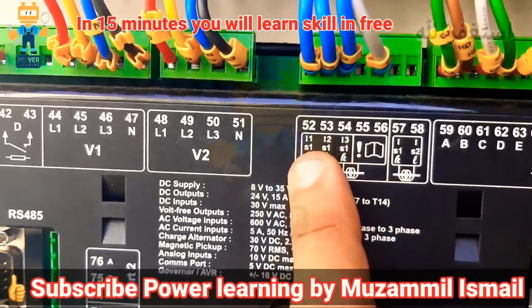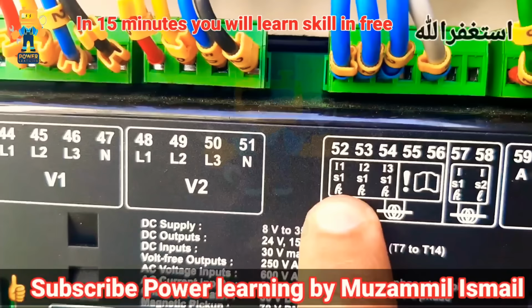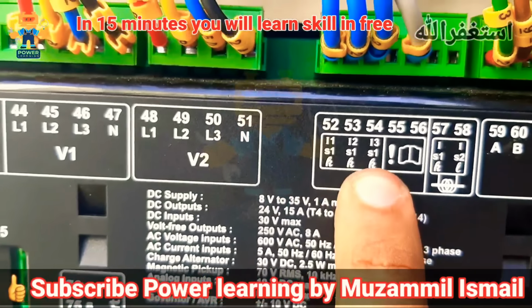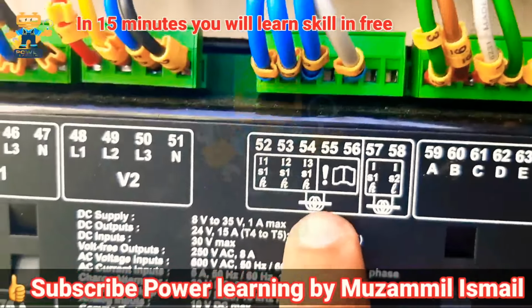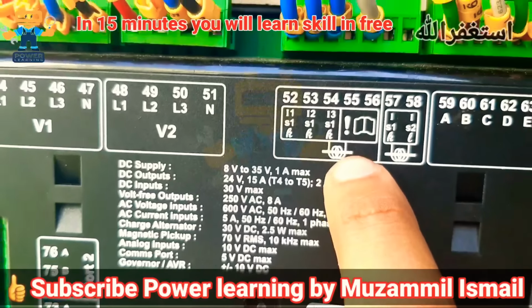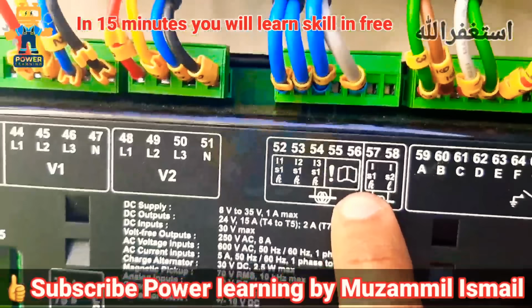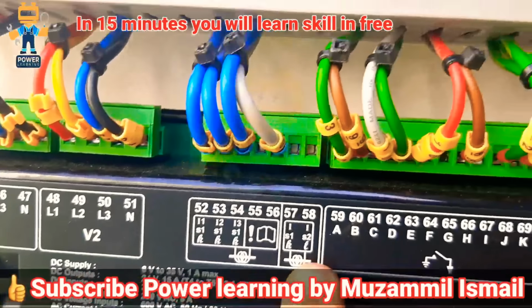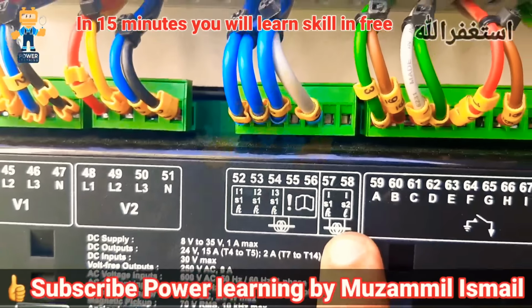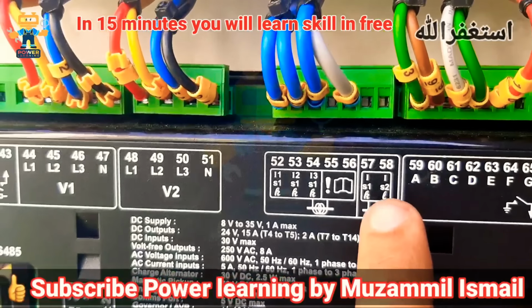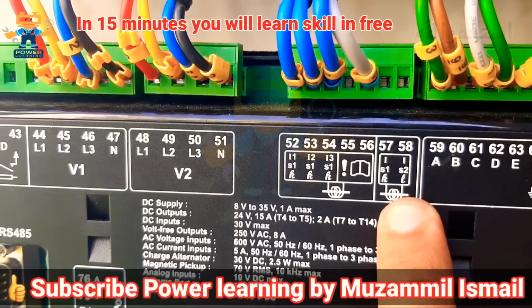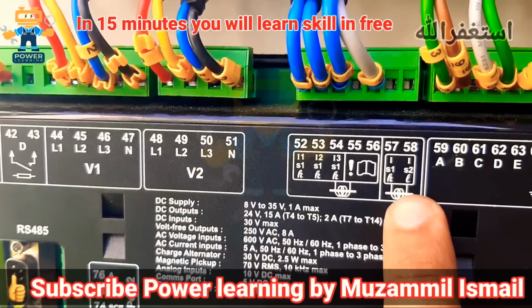Okay, so here we connect on 53, as you see here, I1, I2, I3. These are the 3 CTs, and you see here the CT symbol. Okay, and the common is connected on number 56. Okay, if we are using earth protection, an earth CT, then this CT will be connected here. That's why these two terminals are separate.